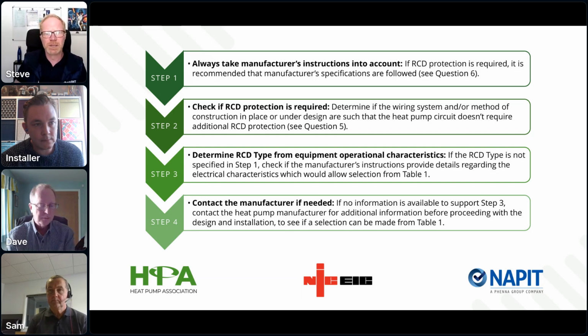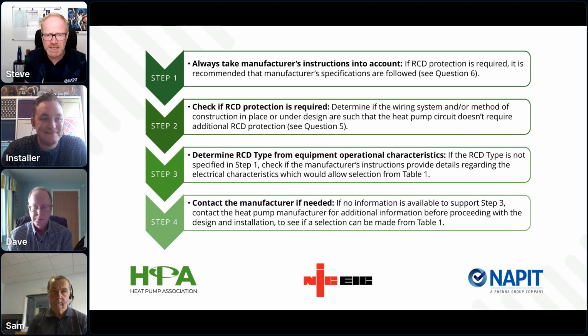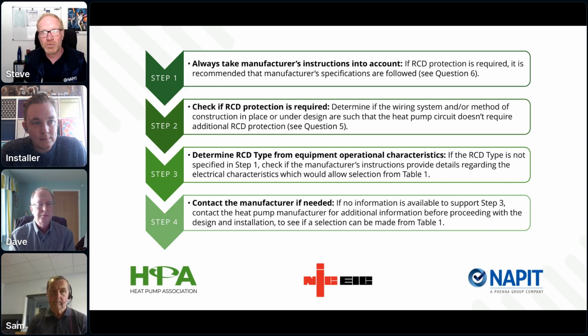But new builds, it's looking at that then where the designer or the project managers of those kinds of installations is thinking out the box a little bit and doing some of the things I talked about, routing the cables sensibly. What is it actually wired in? Is it mechanically protected? And another point worth raising, I don't want to cause more confusion, is what is mechanical protection these days? Impact drivers and drills that are strong these days will go through a knife through butter, literally, as much through a wall and a cable. So we've got to start thinking, can we negate that? So new builds could be an answer depending on the design. And also with retrofit, I would as an installer and a designer be thinking, right, where am I routing this cable? What's the best option? And it might just be that I do need an RCD at the end of it.